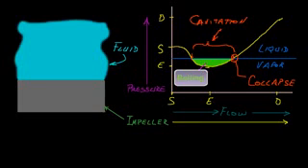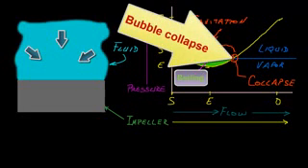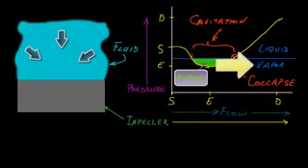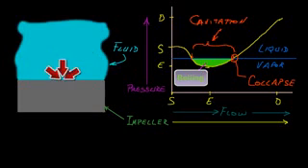Returning now to our earlier illustration, similar to the collapsing balloon that we just saw, as the pressure of the fluid increases during the pumping cycle, at some point, the vapor pressure inside the gas bubble is unable to support the external fluid pressure of the surrounding liquid. At that point, the gas bubble collapses or implodes under the pressure. Or, in other words, the gas bubble vapor quickly changes phase back to a liquid state. The collapsing gas bubble results in a high-velocity, localized, fluid impact shockwave on the surface of the part.